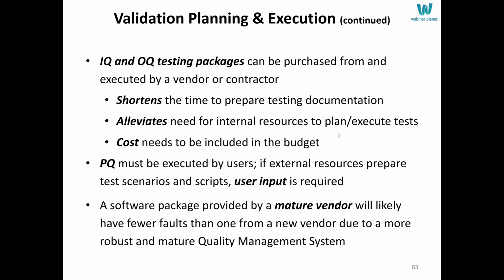They can prepare the test scenarios and scripts, but only if they get direct input from your subject matter experts. And that has to be documented. Once they get that input and write the PQ protocol, they can't execute it. Only the subject matter expert can execute that protocol, but the external resource can write the summary report.